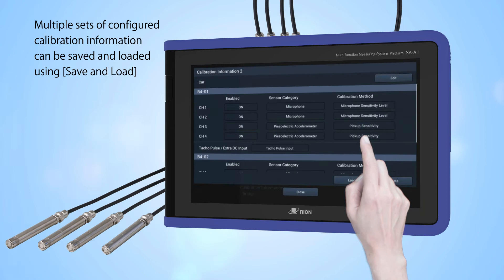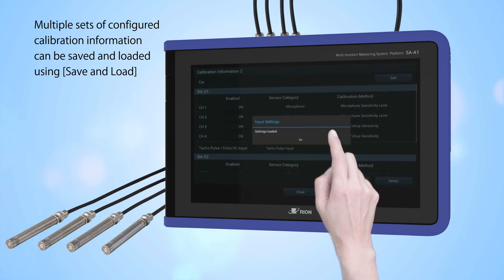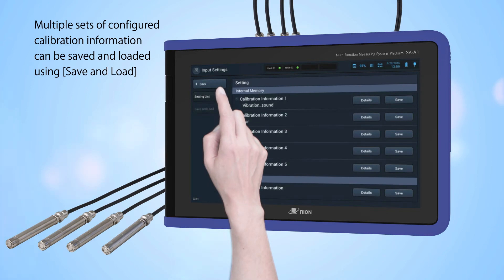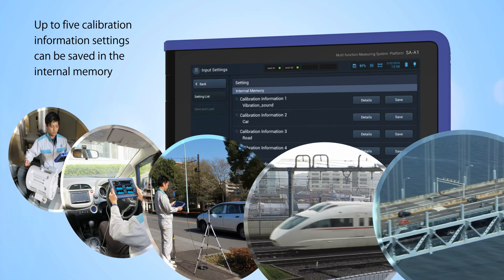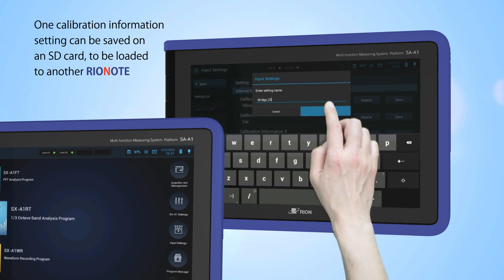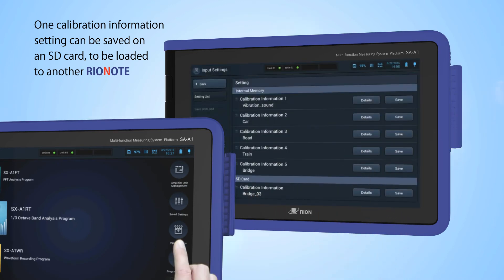Multiple sets of configured calibration information can be saved and loaded using save and load. Up to five calibration information settings can be saved in the internal memory. One calibration information setting can be saved on an SD card to be loaded to another RIONOTE.